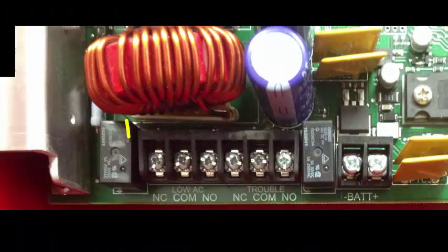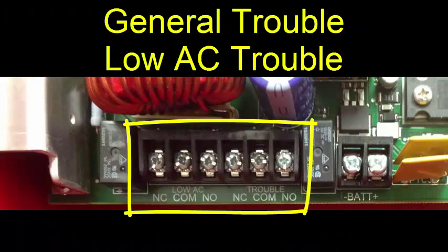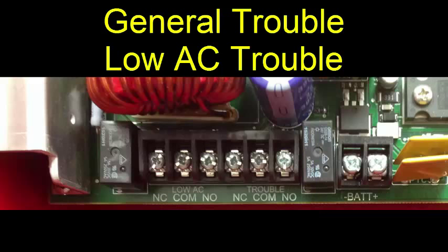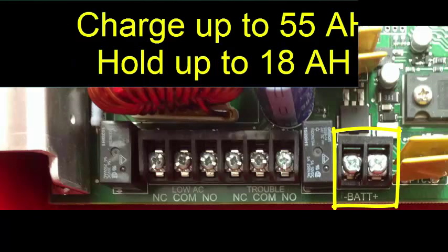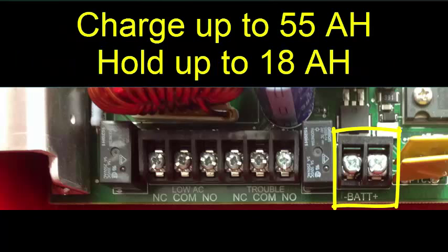There are two trouble relays, general trouble and AC loss. The general trouble relay will trigger when there is any trouble condition on the power supply. The AC loss relay will trigger when the panel loses its dedicated power source. You can also program a delay time for the AC loss relay to trigger the general trouble relay. Moving to the right, we find the battery charging terminals. The panel will charge up to two 55 amp hour batteries and the cabinet will hold two 18 amp hour batteries.